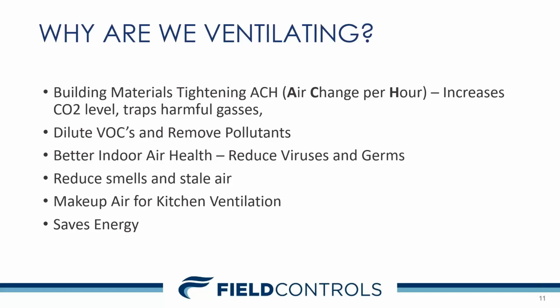And that's where we as Field Controls feel we can fill the gap and provide not only the products and services, but the training to do ventilation in the correct manner. We're also ventilating because we want to dilute the VOCs and remove pollutants, better indoor air health, reducing viruses and germs, reducing smells and stale air, makeup air for kitchen ventilation, as well as being able to save energy, because when you tighten up a home and you put it under positive pressure, you're not pulling in air that's untreated from every corner of the home.